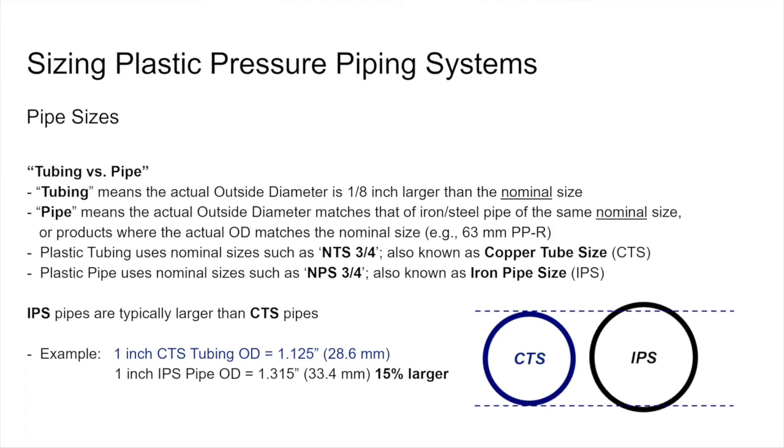Polypropylene pipes are generally produced in metric dimensions where they were first developed. Most polypropylene pipes are marked with a metric outside diameter, like 63 millimeter or 50 millimeter — that's the literal outside diameter. In some cases people co-label the pipe, so a 50 millimeter pipe might also be marked as a one-and-a-half-inch pipe, because that's the closest steel size. Those are generally the three different sizing schemes in use: CTS tubing, IPS pipe, and metric polypropylene.